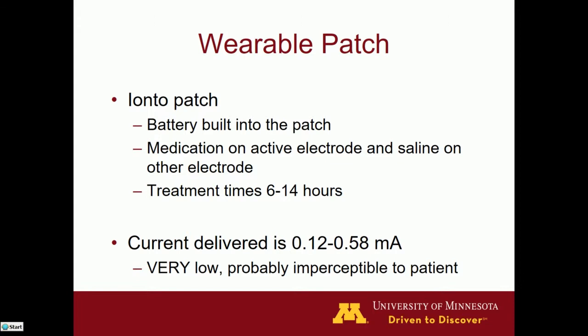With the wearable patch, dosage is different. You don't really get to set any of those parameters like you do on a clinic unit. The battery is built into the patch. There are no settings. It's based on the patch you choose to use. The electrodes hold a certain amount of medication depending on the size and how the company who makes the patch designs it. Like I said, it has a built-in battery, and the medication is placed on the active electrode and saline on the other electrode.